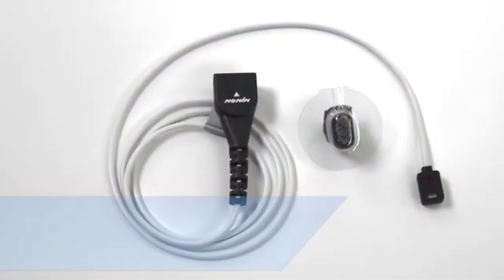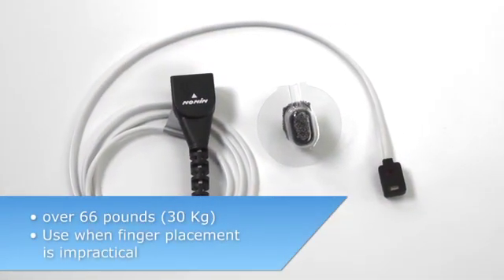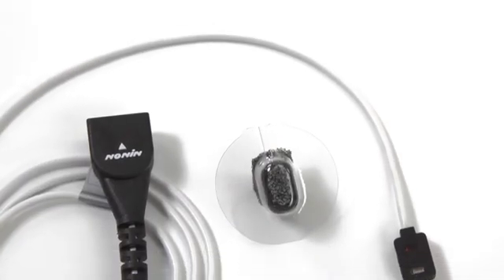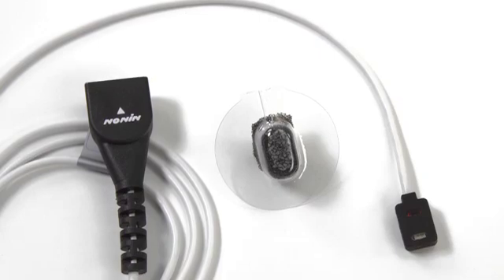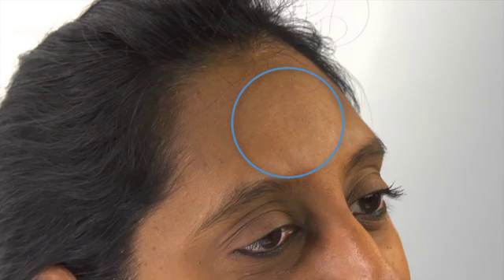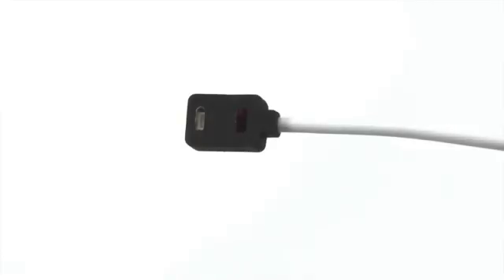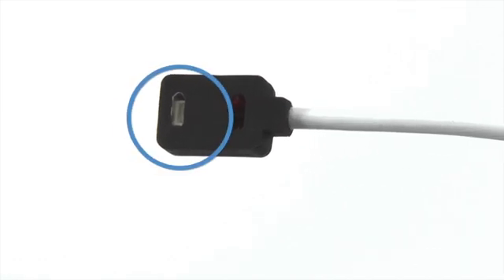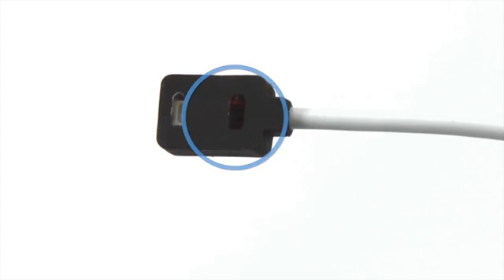The Nonin 8000R sensor is designed for patients over 66 pounds, or 30 kilograms, where a finger sensor is impractical. This sensor adheres to well-perfused, flat skin, typically on the center of the forehead with a Nonin 8000H sensor holder. The forehead sensor emits a special light wave pattern into the arterial blood flowing in the forehead, and the adjacent detector receives reflected light back from the site.